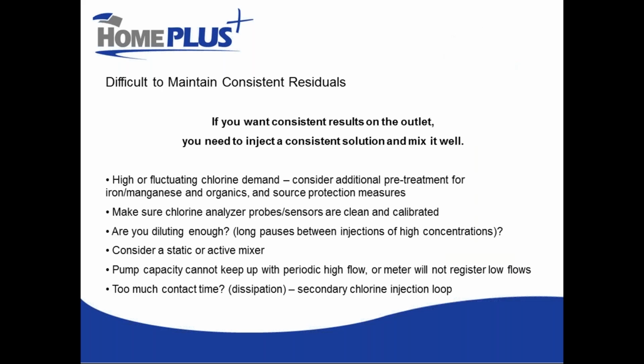Difficulty in maintaining consistent residuals often is due to fluctuations in your chlorine demand, which we just talked about. If you're measuring your residuals using a chlorine analyzer with probes and sensors, those probes and sensors need to be cleaned and recalibrated often. That's kind of a little bit of the bane of chlorination systems for small treatment plants, because they often require more maintenance than the value they provide.